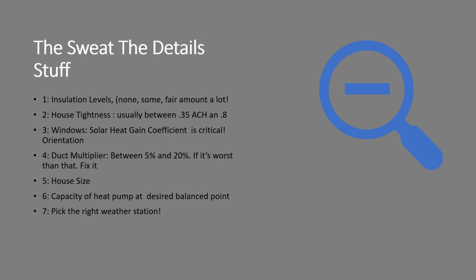House size is important, but not as important as insulation levels, window U values, and window orientation. You need to know the capacity of the heat pump at your desired balance point. You can do that either by direct lookup or by drawing the traditional balance point diagram. And also, don't forget to pick the right location. Remember where you live.